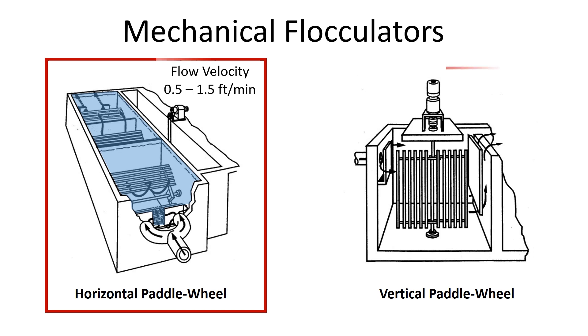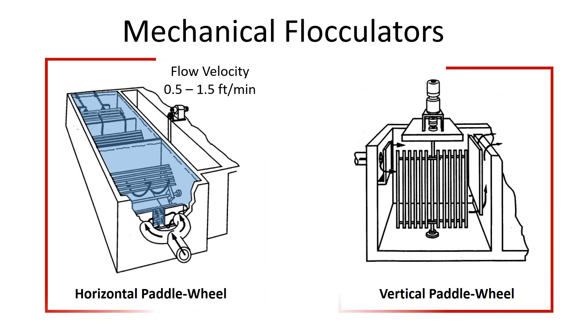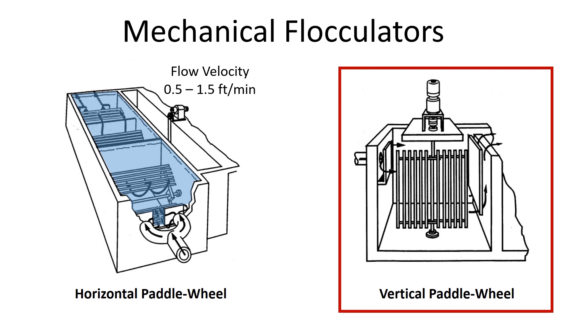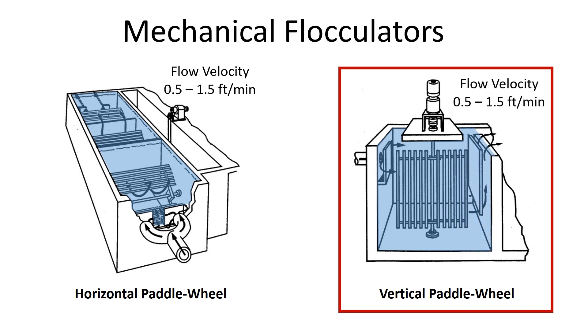The vertical paddle wheel has paddles that are vertical and rotates gently to provide the mixing energy, with water moving from one side to the other. Again, at a flow velocity of 0.5 to 1.5 feet per minute. We want this water to move through very slowly with varied mixing energy in each of the three chambers.